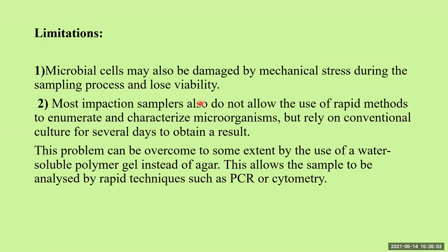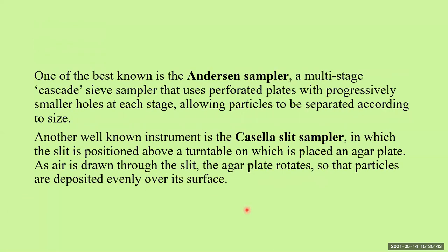Limitations of impaction samplers: microbial cells may be damaged by mechanical stress during sampling and hence may lose their viability. Most impaction samplers also do not allow use of rapid methods — conventional culture methods are typically used. This problem can be overcome by using a water-soluble polymer gel instead of agar, which allows the sample to also be analyzed by PCR technique.